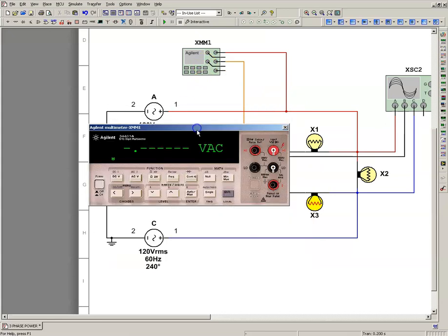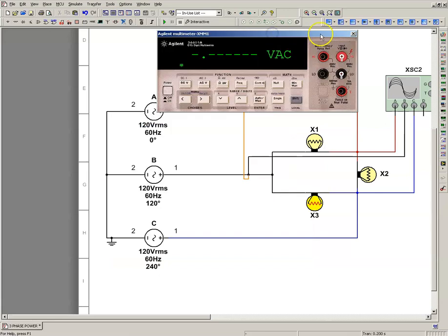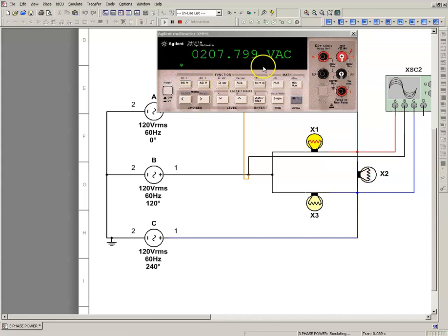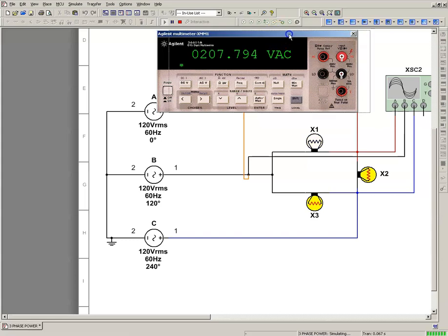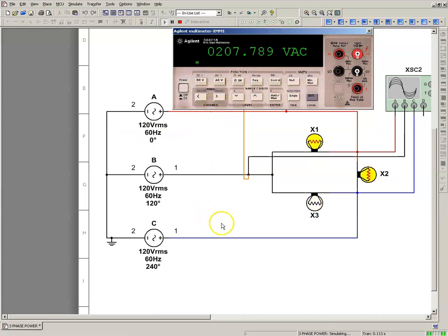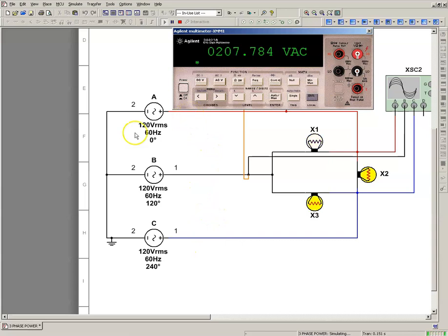I have my Agilent meter connected, I'm going to run it right now. 207.85, so let's just say 208 volts - that's a common system voltage in a building. That's 120 volts times the square root of three. If you measure from line to line it's going to be 208 volts - from line A to B, B to C, and C to A. If you measure from A to the common X zero or neutral point it's going to be 120 volts. So there you have it, a basic three-phase system.